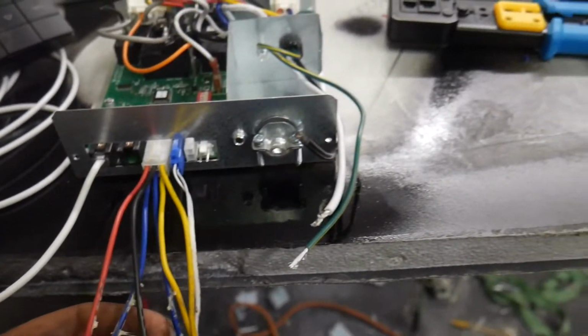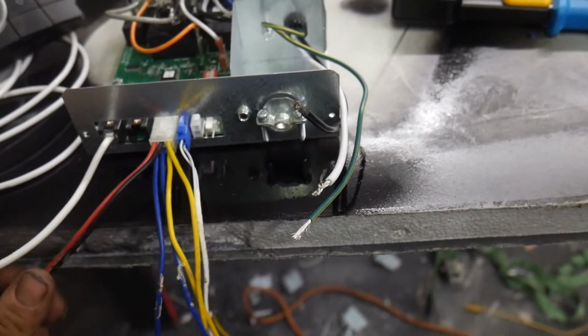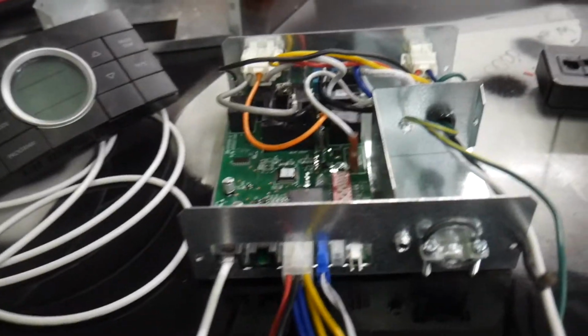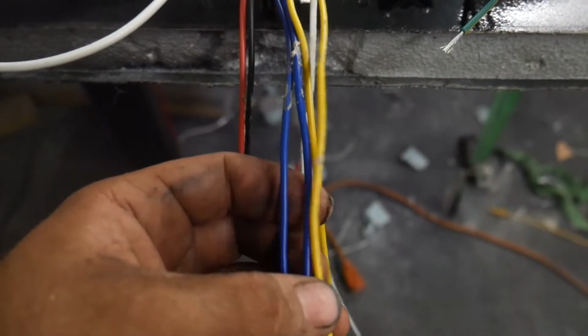It kept having an error code. But what I wanted to show is it's got 2 extra relays in it that you can do several other things with, and one of them is what they call a load shed. So anyway, the deal with the load shed relay - and I don't remember exactly what I explained, I'm probably going to repeat myself here - is it's basically another relay that corresponds with the compressor relay. So when the compressor kicks in, it closes a single pole, single throw relay set of contacts. And what I'm going to do is loop in series all 3 of these sets of load shed contacts, so that whenever all 3 compressors run simultaneously, it'll have continuity between those 3 sets of contacts.